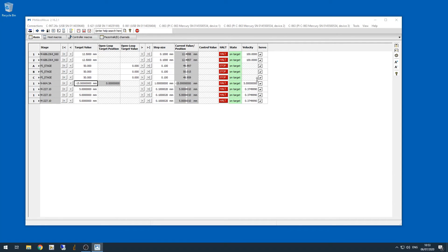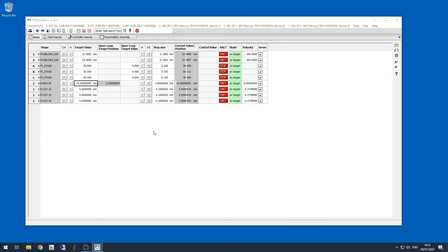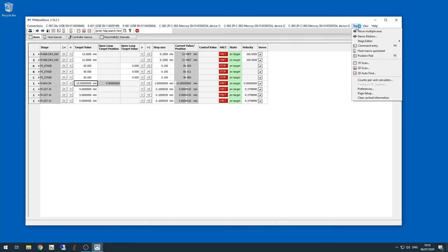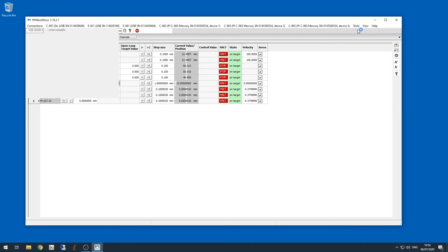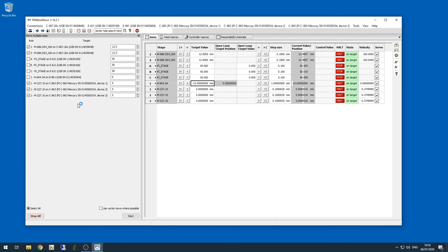Okay, so now we've connected to all the controllers, all the servos are on, and everything shows as on target, so we are ready to go. Now if you're still setting up your system and you want to move the sample stage stack up or down to get a good initial coarse z position, go to the tools menu and choose move multiple axes. That opens up the window on the left, and you can uncheck the things you don't want to move, but we'll leave the three checked that we do want to move.